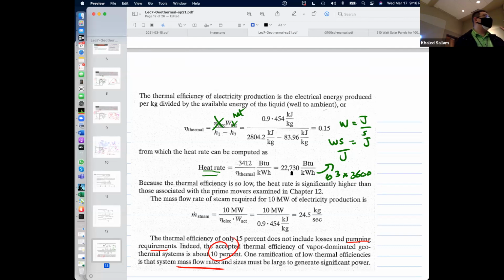So when this number goes up for them, they get panicked because now they are not making money. So we are selling it for 11 cents the kilowatt hour, and they are paying a lot of money because they are using a lot of BTU. That happens when the power plant runs at partial load. When they're rather running at full load, and someone says 'we don't need all this power, go down,' when they go down, the efficiency dropped. Those steam power plants are designed to run at full load. So once you cross 10,000, 11,000, that is horrible.